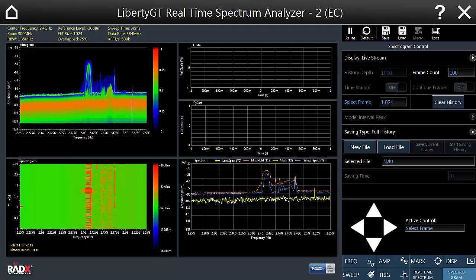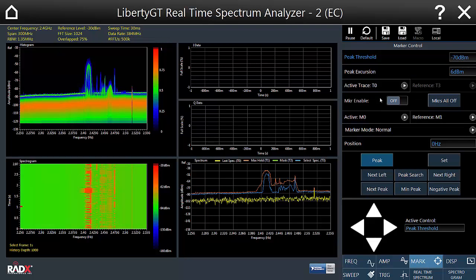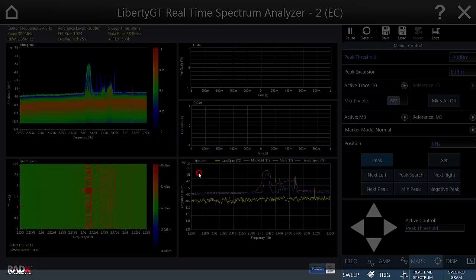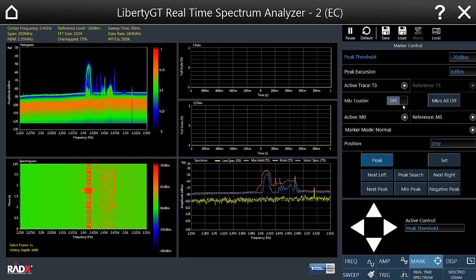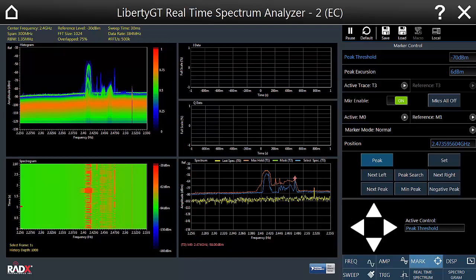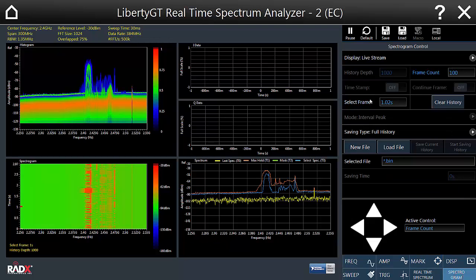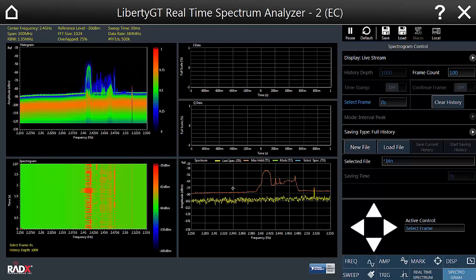If you want to do a more detailed analysis of the signal, you can use markers. First select the trace you want to perform a marker search on, then enable the marker and do a peak search. This reads out the position of the peak in the spectrum and the signal level at that peak. We'll then get things back to a default state with just the current spectrum and maximum hold displayed on screen.